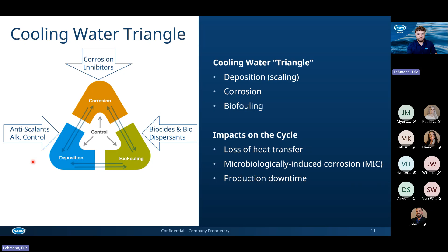Some other parameters we might see when it comes to cooling water or cooling tower management: pH is a big one. Conductivity, we talked about TDS, conductivity, alkalinity, hardness. Sometimes we see iron being monitored to see how much iron is being removed or transported from the cooling tower itself. Turbidity is another big one, maybe organics. Turbidity is a good indication of solids coming through that cooling tower, kind of on that recirc line.